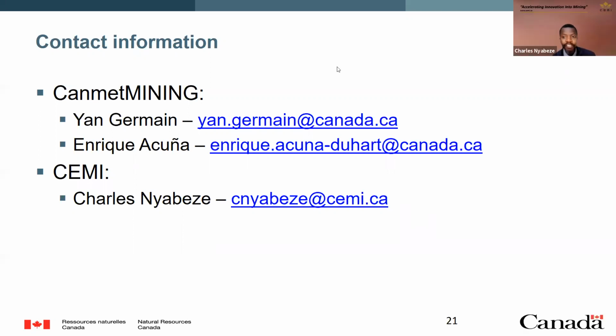And another question here is from Charles, and the question is, what are some current examples of heat capture and reuse? And maybe if I can just jump in, Enrique, on that one, we are aware of an air-to-air heat exchange system that is being manufactured by a company called Gupex out of Norway. They take low-grade heat coming out of the ventilation system, and they capture that heat, and that heat is reused to offset the cost of heating air that's going back underground in colder climates. So Enrique, maybe you can give us some other examples of heat capture and reuse that's happening out there.